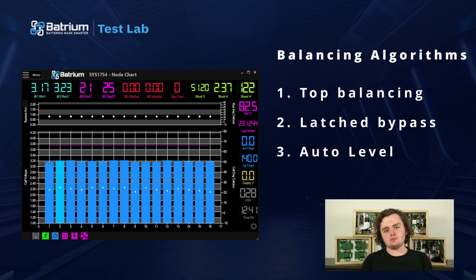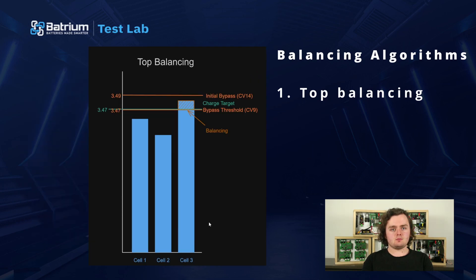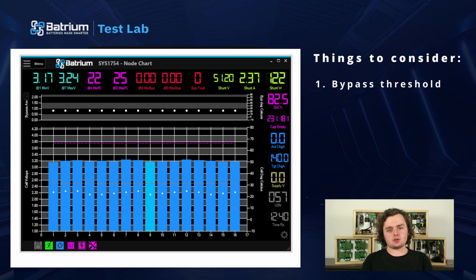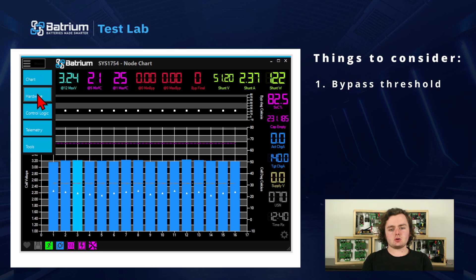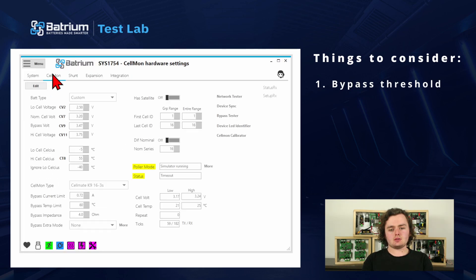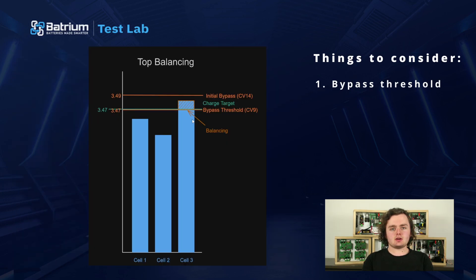To start, the basic algorithm that the others build on is called top balancing — this refers to the way it operates at the top of charge. There are four variables to consider. The first is your bypass threshold, marked in the toolkit software as CV9. You can find it under hardware settings, and you can see it on the graph as well.